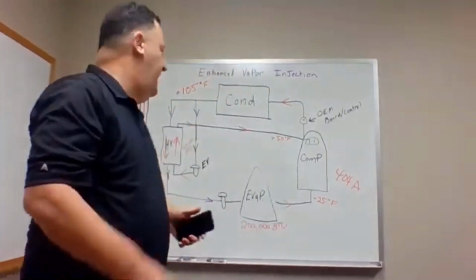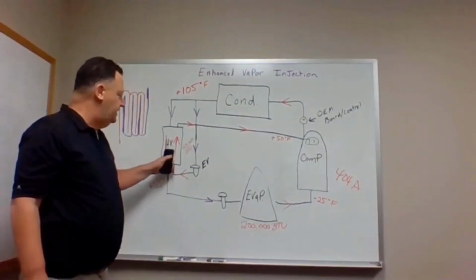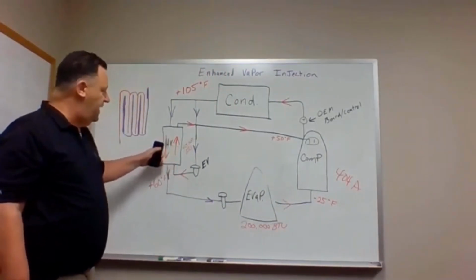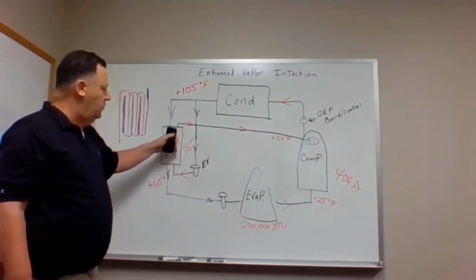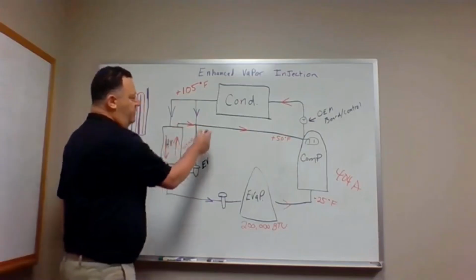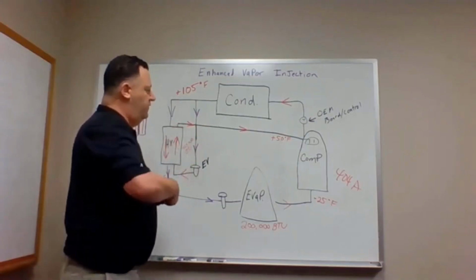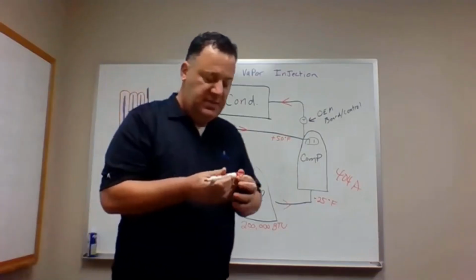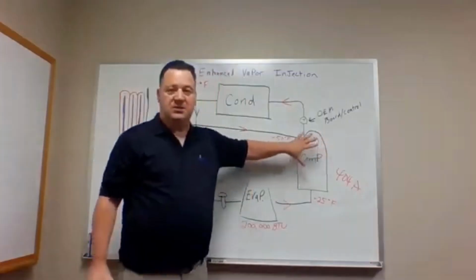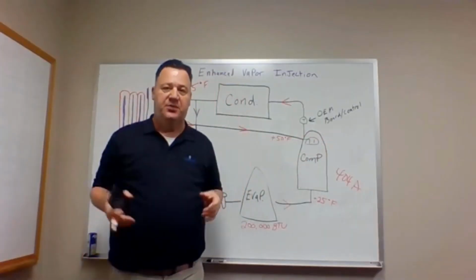Now, going back to this here on the vapor side, we picked up that heat, removed 45 degrees of the subcooled liquid. We picked up that heat. We're a vapor over here. So as we know, when we raise the temperature, we raise the pressure. And the whole idea of the compressor is to raise that temperature and that pressure, right?